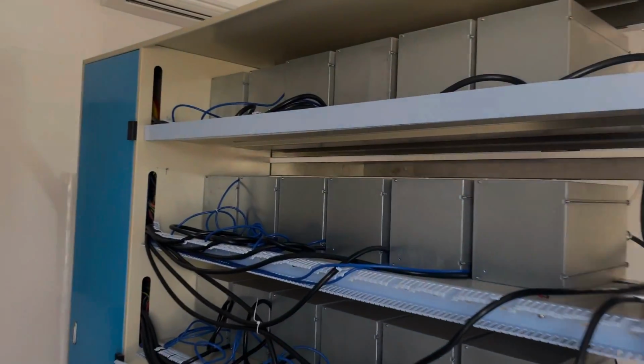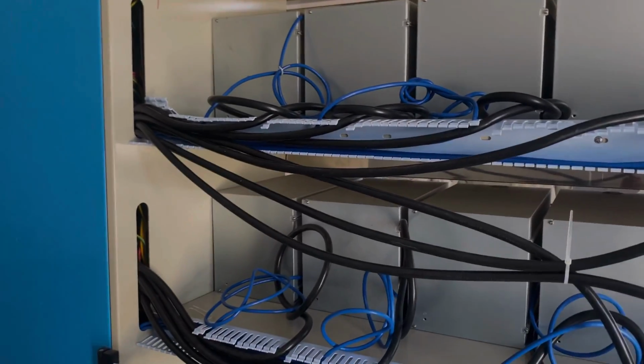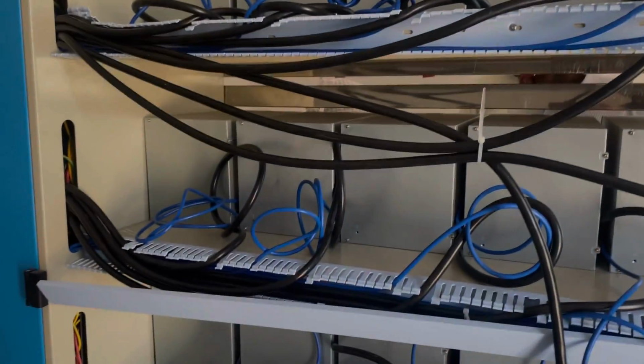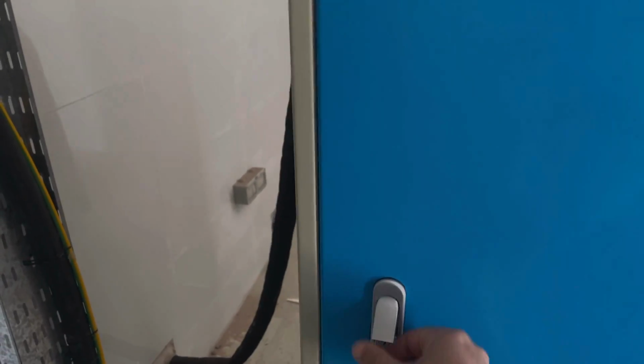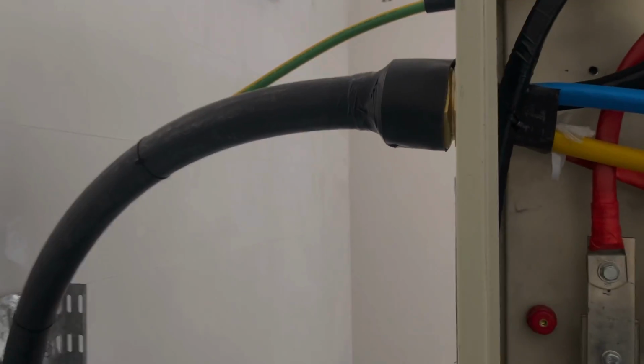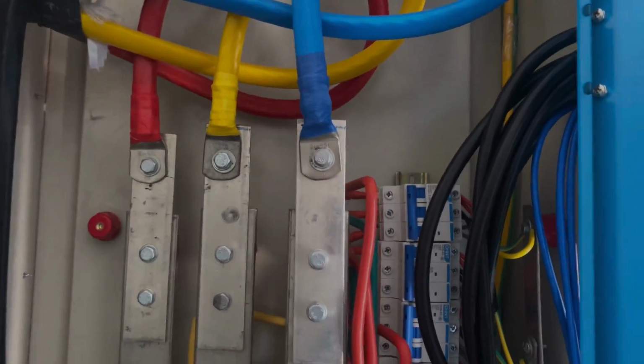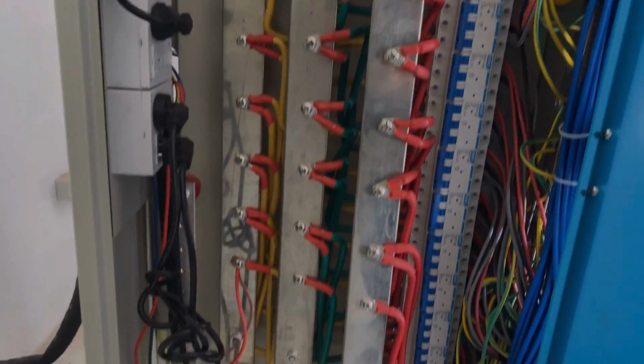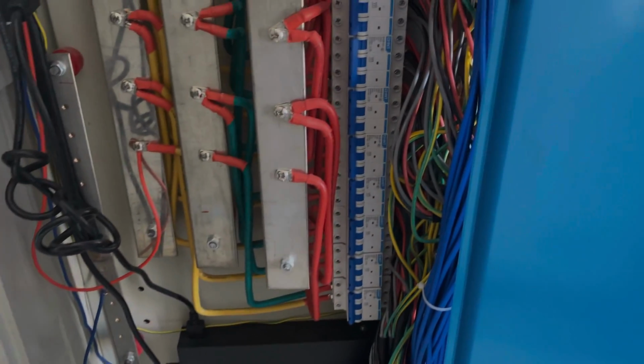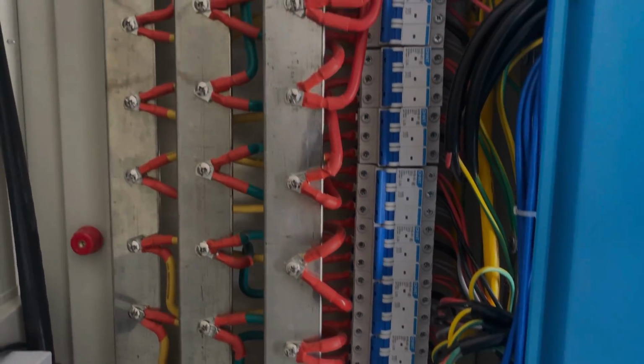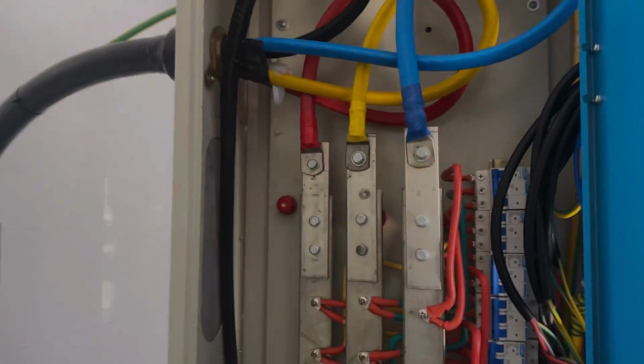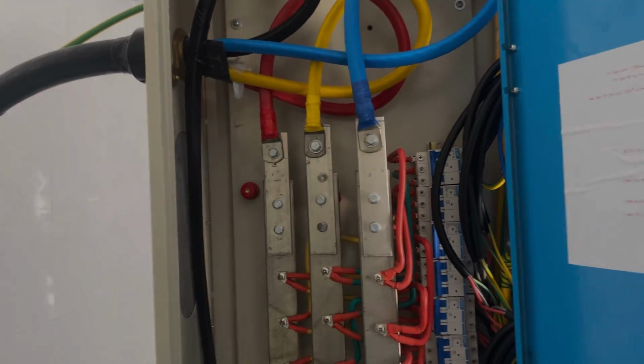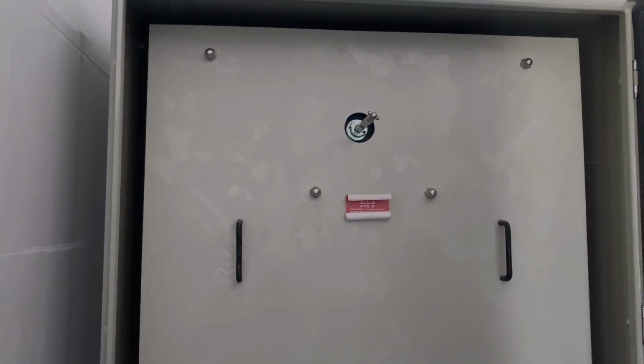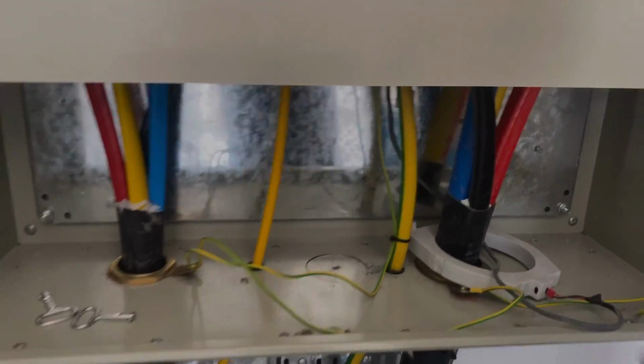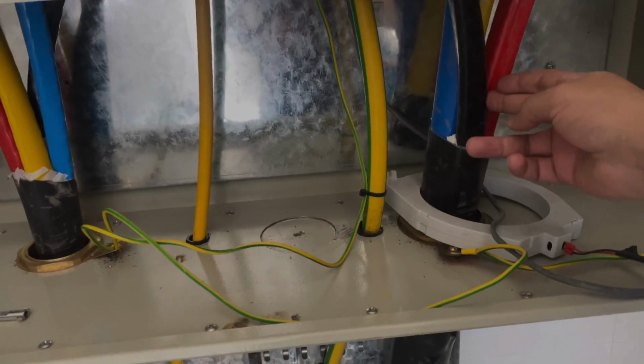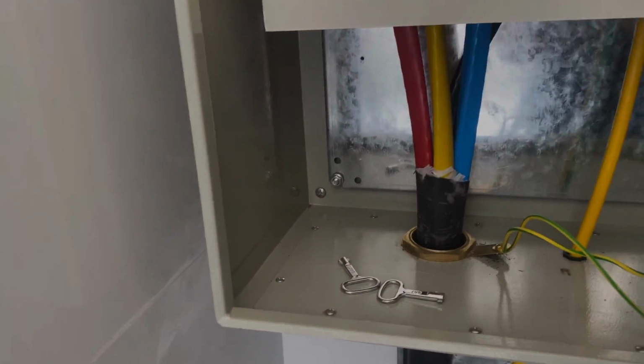Now let's go to the back side. As you can see, all the wiring is running here. We're still doing some wiring, which will be finished in a minute. I'll show you the power distribution box from the cabinet itself. We see the 180 millimeter cable coming in. The whole thing is installed inside, including individual breakers rated at 63 amps, because these miners run on 380 volts 3-phase power. We have the main power box here. This cable is coming out from the power room. This is a 240 millimeter, and this is the one going to the cabinet.